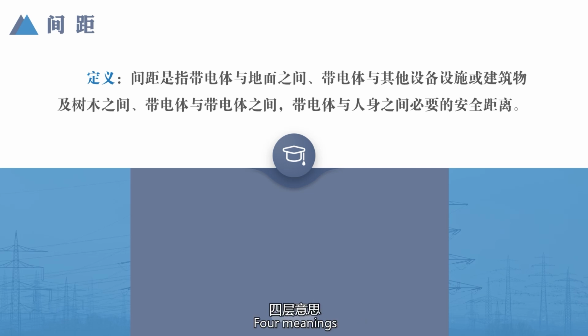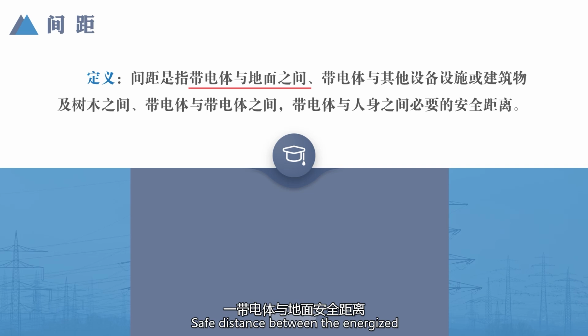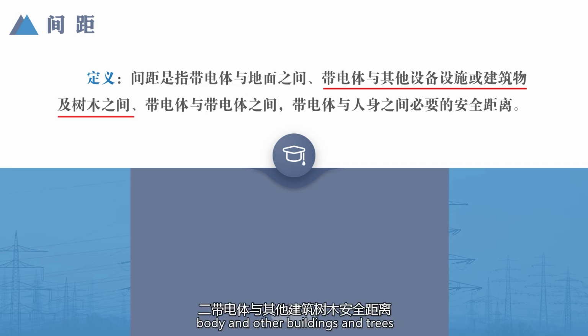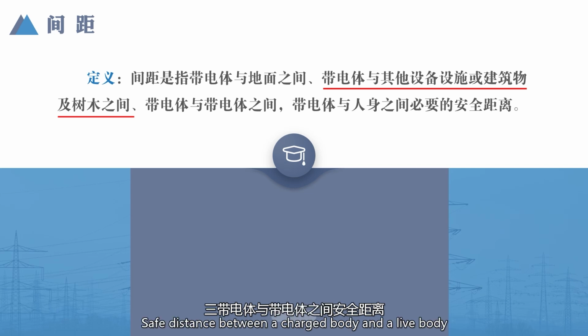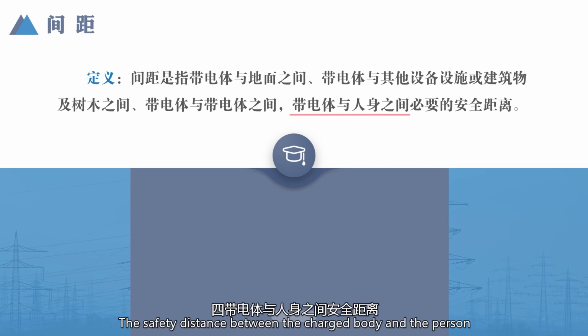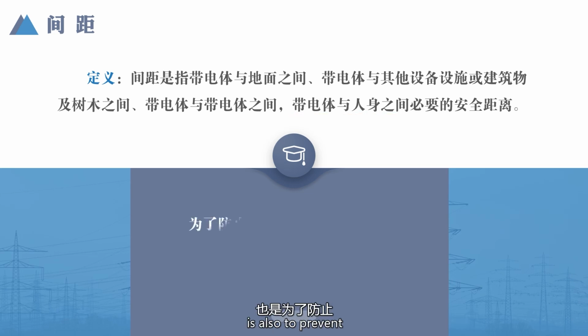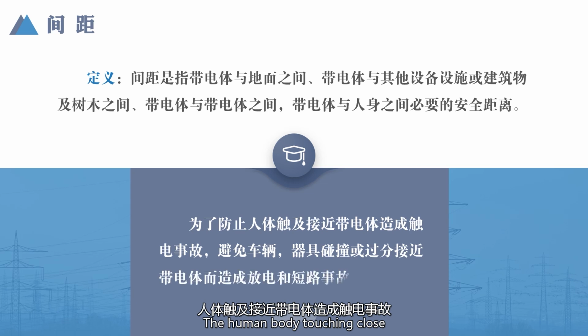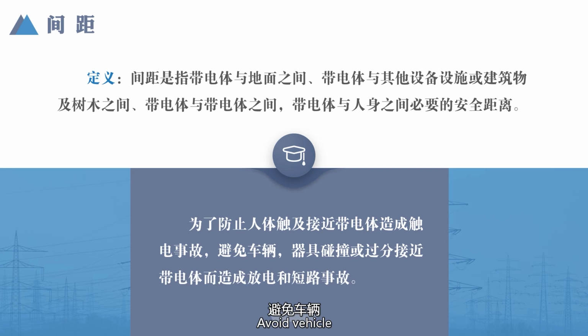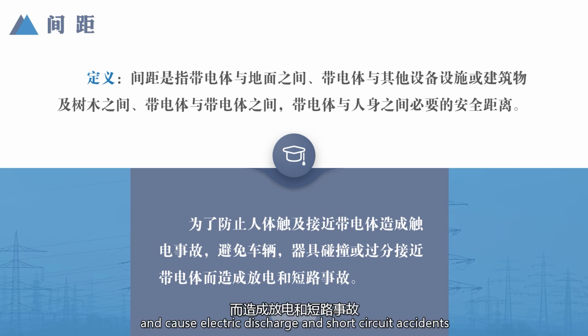Necessary safety distance has 4 meanings: the safe distance between the energized body and the ground; the safety distance between a charged body and other buildings and trees; the safe distance between a charged body and a live body; and the safety distance between the charged body and the person, which is also to prevent electric shock accidents caused by the human body touching or getting close to the electrified body. It also avoids vehicle or apparatus collision, or getting too close to the charged body, which causes electric discharge and short circuit accidents.